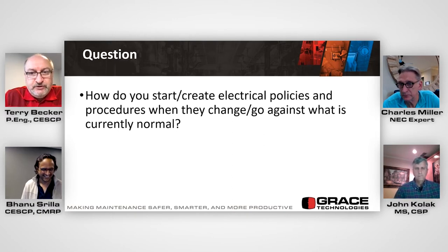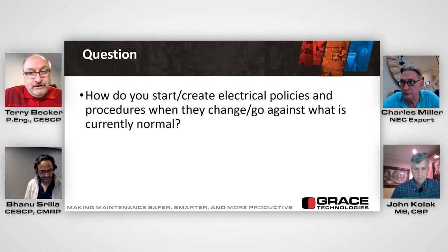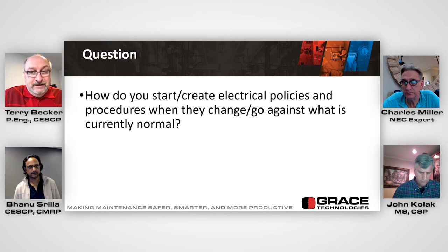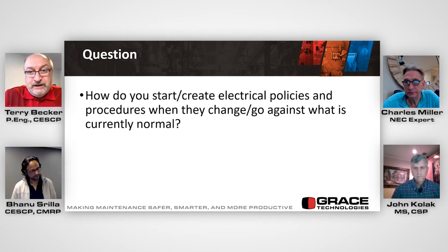Every 3 years, you should be reviewing your established policies, practices, and generic procedural requirements. And then along the way, I recommend an annual review too. If you look at the auditing requirements of 70E, in Article 110.5 under Electrical Safety Program, they say that your electrical safety program should be field audited. So that means right now the supervisor needs to be doing what I call a supervisory level audit every hour, every day, every week, every month, and they need a tool to monitor that.